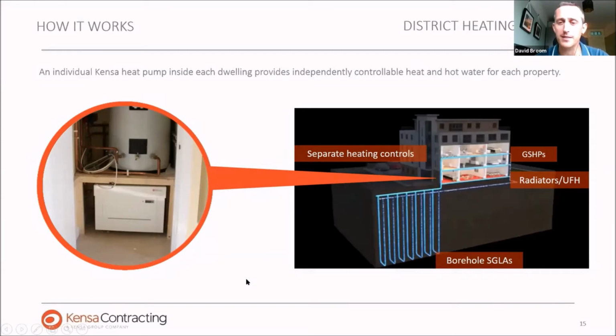What basically happens is if on that large circuit, a single heat pump is calling for heat, that one little circulating pump within the heat pump has enough power to deliver the flow rate that one heat pump needs. And then as more heat pumps turn on, more circulating pumps turn on, and then the flow rate increases. And then providing that the design is done such that the combined head of all of the pumps operating can overcome the resistance of all of the pipes that are connected to it, we'll always get the amount of flow that we need dependent on the number of heat pumps that are operating.